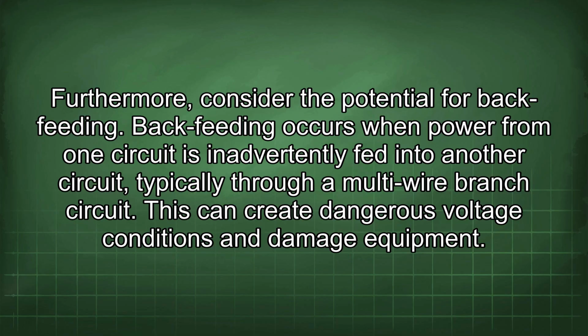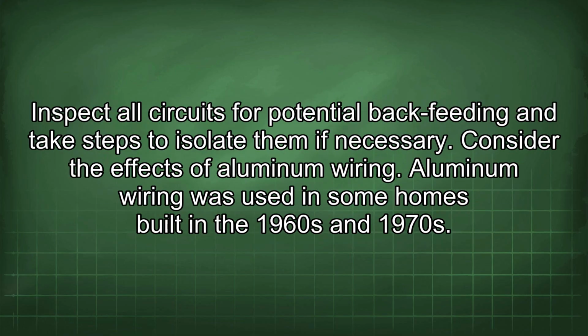Furthermore, consider the potential for backfeeding. Backfeeding occurs when power from one circuit is inadvertently fed into another circuit, typically through a multi-wire branch circuit. This can create dangerous voltage conditions and damage equipment. Inspect all circuits for potential backfeeding and take steps to isolate them if necessary.